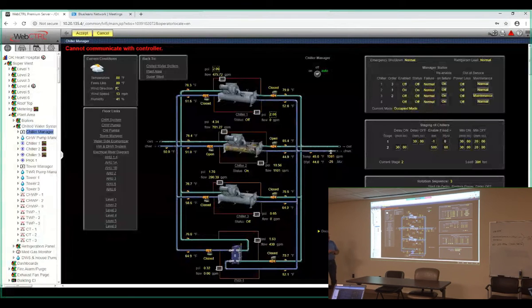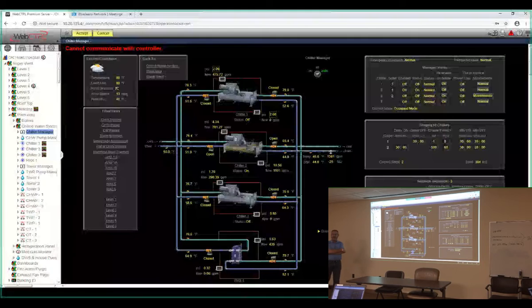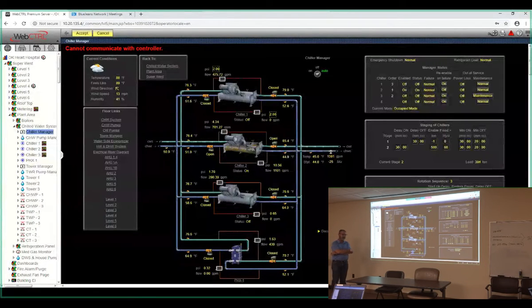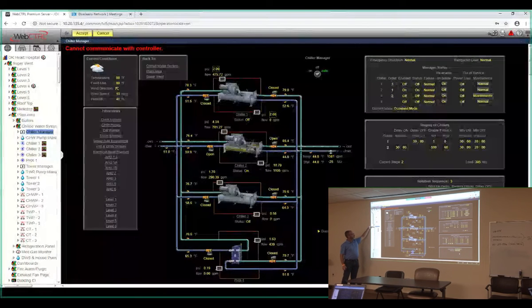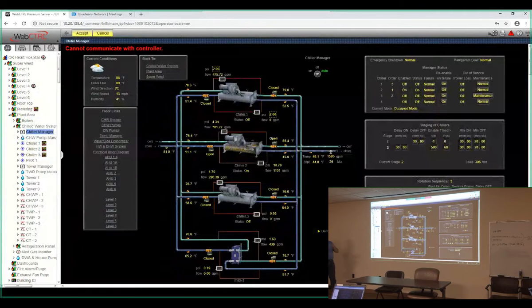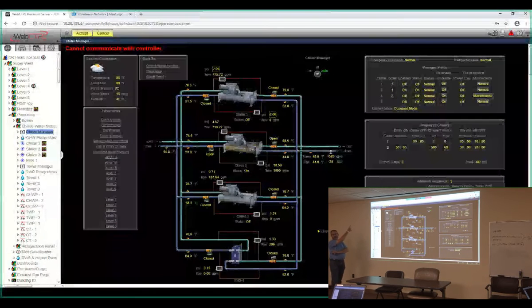I usually like to do my plant rotations and stagger them. So say if I'm going to do it at 1 o'clock in the afternoon, I'll do my chillers first, do my chill water pumps at 10 after 1, do my towers at 20 after 1. I like to stagger them and let them go through so that I don't just switch everything at once, because if you do have a failure, then you get a little overwhelmed with what happened. And you can delay your restarts. So I like to do it staggered by 5 or 10 minutes, let everything cycle through. Maybe it takes an hour to rotate the whole plant. And did you? Go ahead and accept that. Okay.